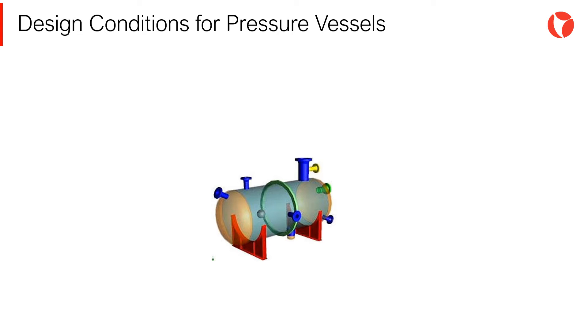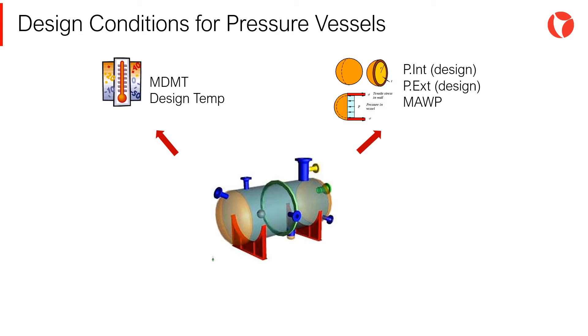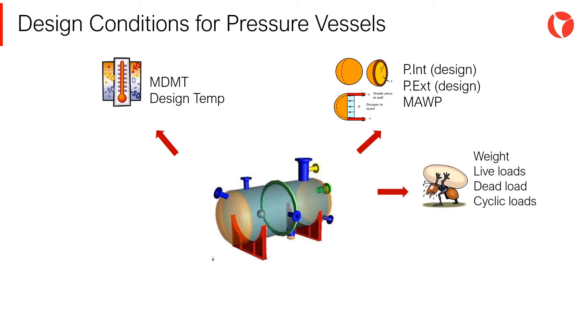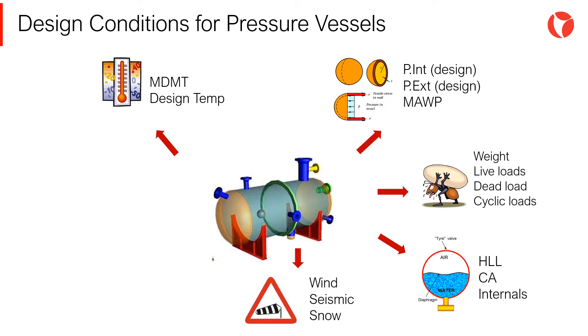Pressure and temperature are just two of the many design constraints that should be taken into account. Some of them are: temperature — ambient temperature, MDMT, design temperature; pressure — operating, design, MAWP, test pressure; loading — dead loads, live loads, cyclic loading; corrosion allowance or liquid level; wind and seismic conditions; steam out; hydrostatic test requirements; and transportation and lifting conditions. Material selection and pressure vessel design depend on these design conditions.